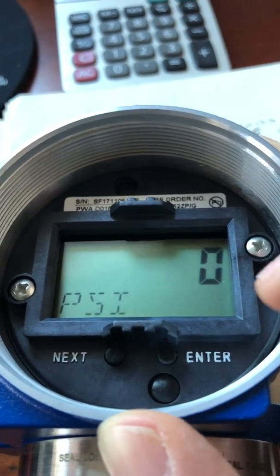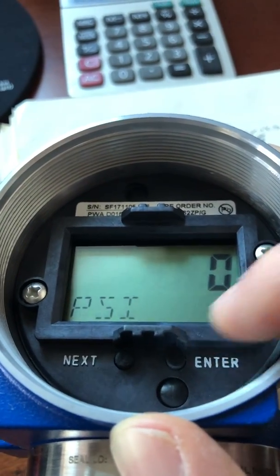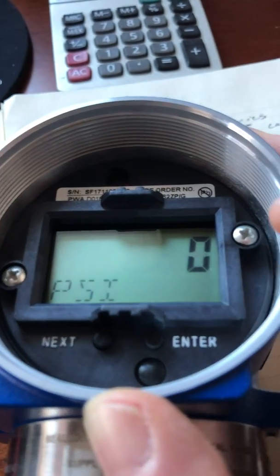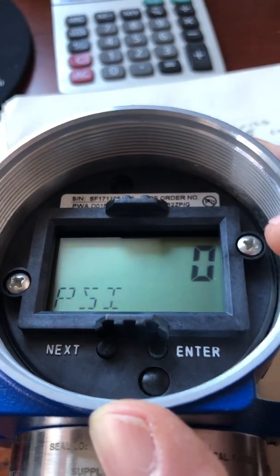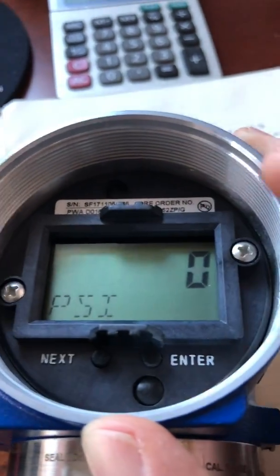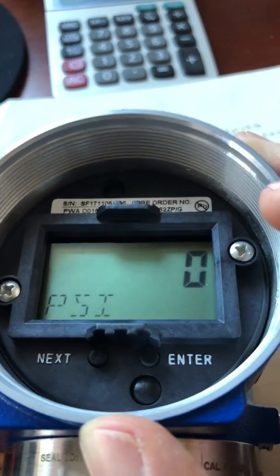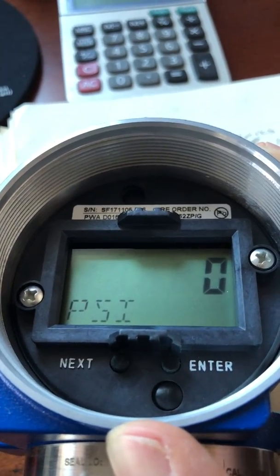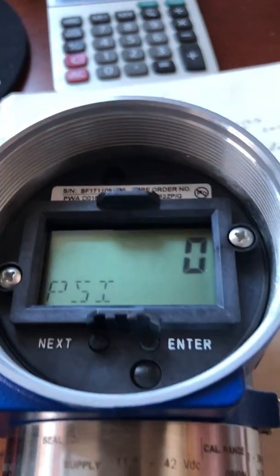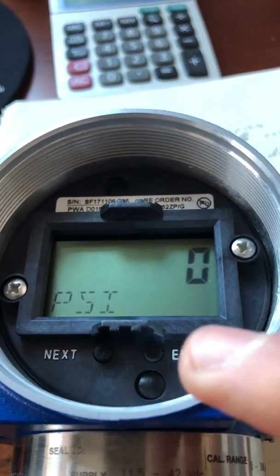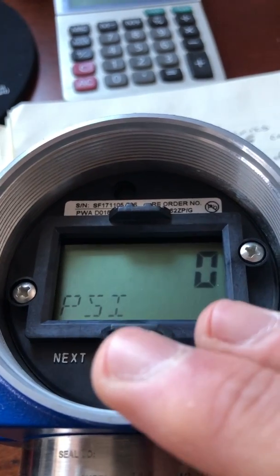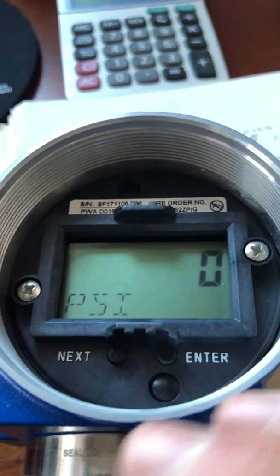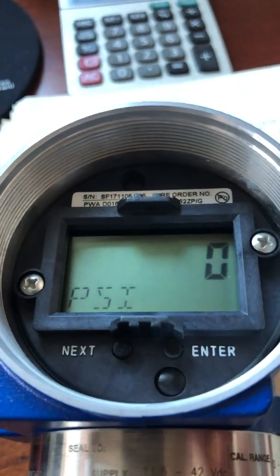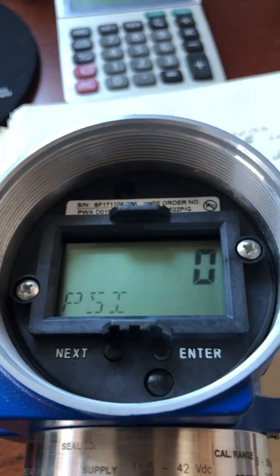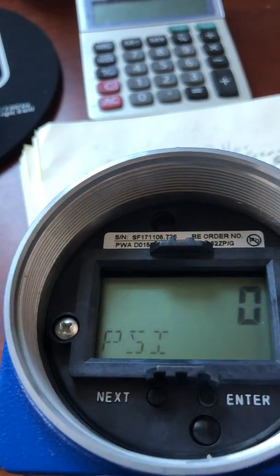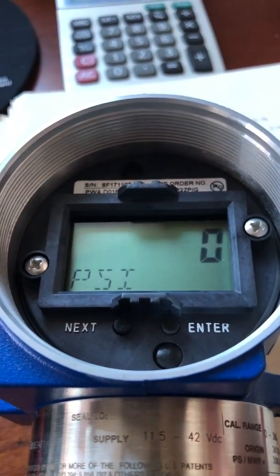And Foxboro pressure transmitters have these displays. Make sure you ask for the display. And you don't have to have a configurator, no handheld, nothing. You just do those few button pushes and you're golden. There's also HART versions of this where you can plug in and use a HART communicator if you wanted to. But a lot of technicians love just opening this thing up in a non-classified, ventilated area, of course, in case it's an explosive environment, and just do everything on the two buttons. And you're good to go.